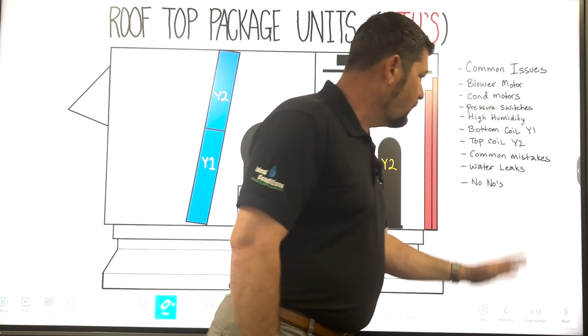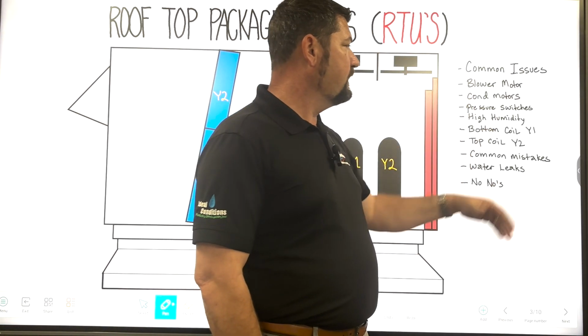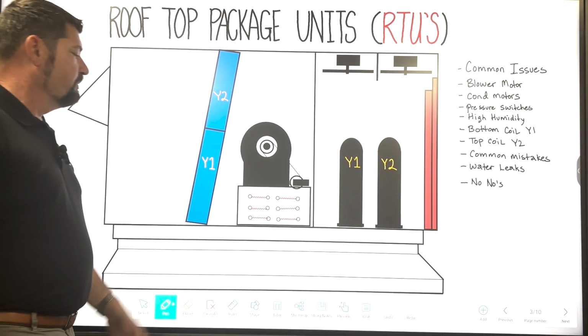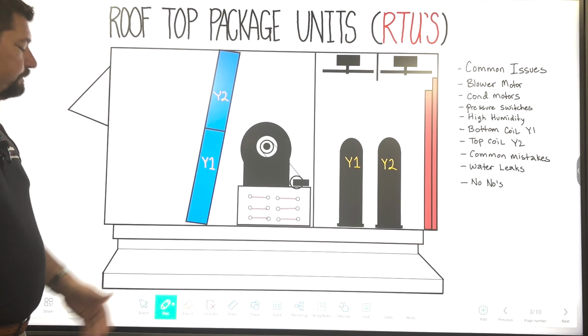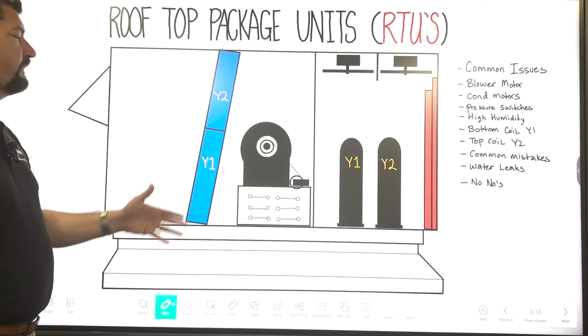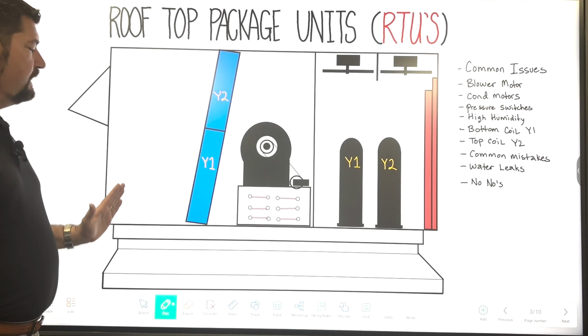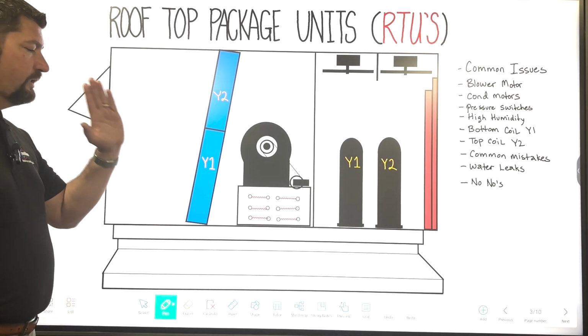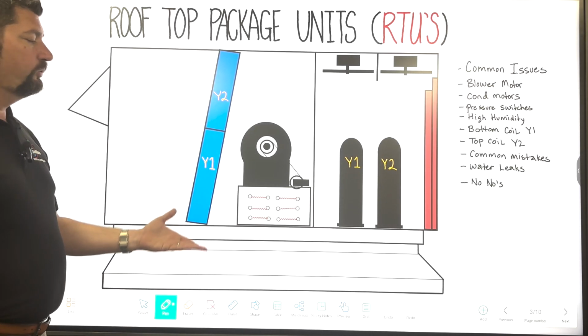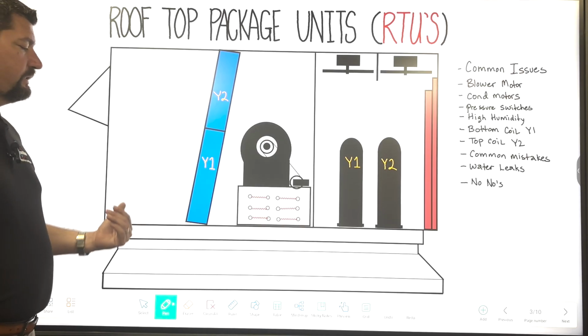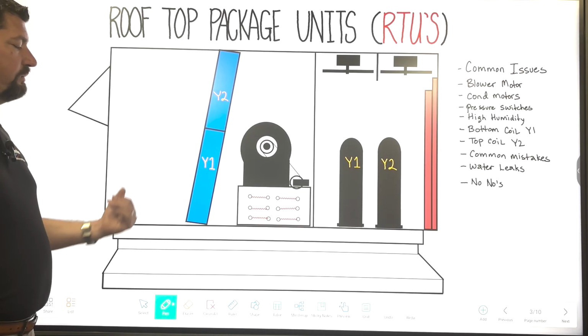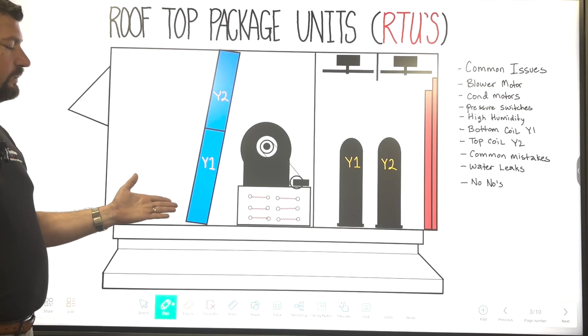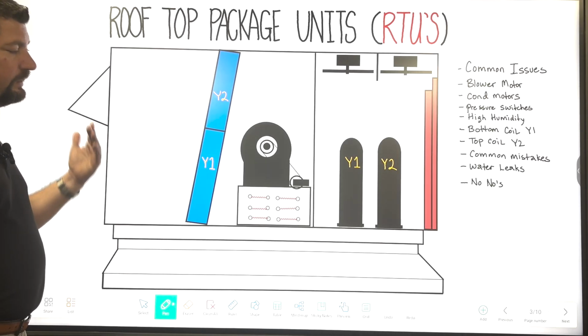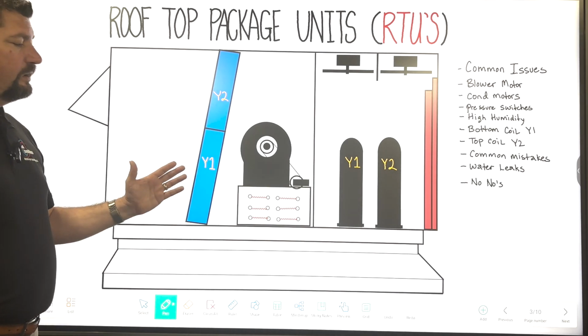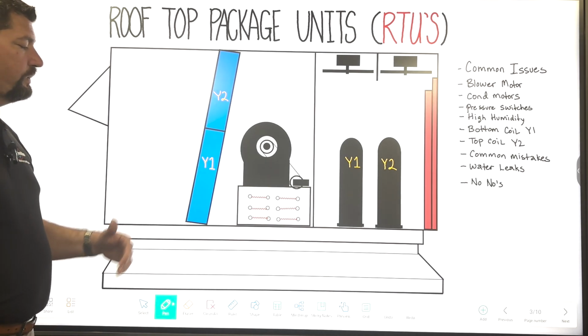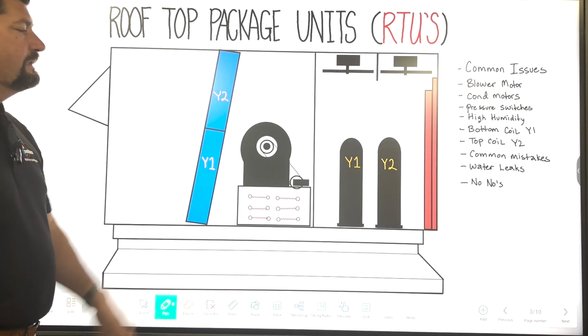So we're going to go ahead and talk about the humidity concerns in the Y1 and Y2 a little bit more in detail. I'm going to move out of the way a little bit so you can see this evaporator coil. This evaporator coil is going to dehumidify the moment any moisture comes in contact with this coil, because the coil is cold. And so it's going to wind up sweating as a result of humidity. If there's less humidity, there's going to be less sweat. The more humidity, the more sweat. So you can't sit there and say, well, it's not draining water off of it. Well, the humidity may be low enough to where it's not going to pull enough water out of the air going across this coil as it would on a more humid day.